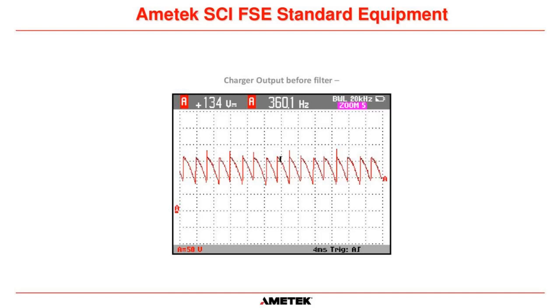This is a charger output of one of our UPSs before it gets to the filter circuit. And we know what that waveform should look like. On this example here, this is a 6-pulse, a 6 SCR charger. Okay, and it's a 60 hertz system, so 6 pulses at 60 hertz will give you 360 hertz. So we know just by taking this oscilloscope picture that that charger is working correctly.